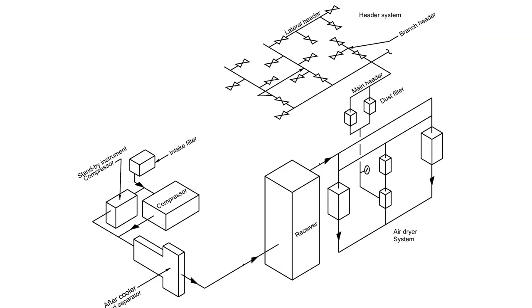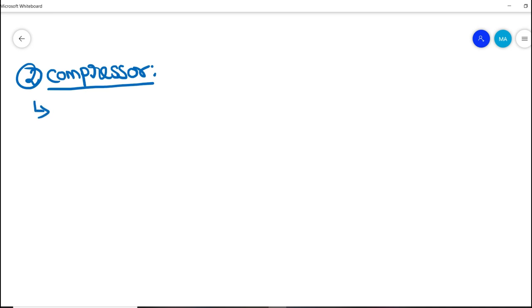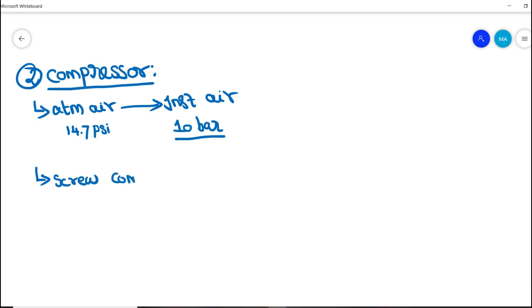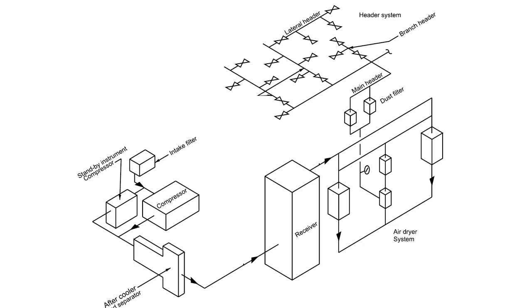Now let's look at the compressor. The compressor compresses atmospheric air into instrument air. Atmospheric air pressure is 14.7 psi, and the compressor compresses it to a nominal range of 10 bar pressure, though some process facilities operate at more than 10 bar. In major industries, screw compressors are used for their efficiency and performance, while reciprocating compressors are also found in some facilities.